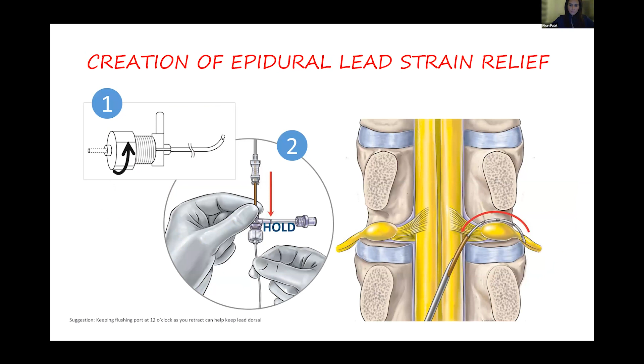So first step, so you're happy with your lead. I always say give yourself a little bit extra, especially when you're first starting to do these cases, meaning although your electrodes 2 and 3 are directly underneath the pedicle, push the lead out a little bit further, because when you make the loop, it's going to pull it back in. So first step is to pull about 5 to 10 centimeters of the stylet out of the lead, so the lead is a little bit floppy.